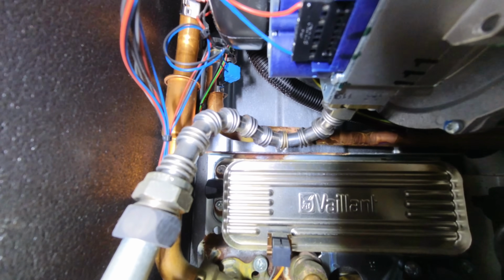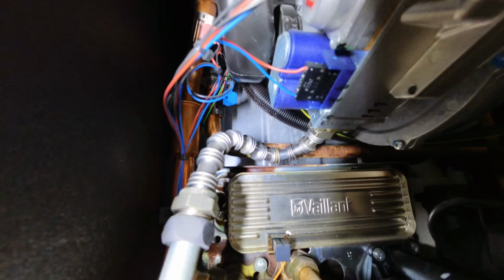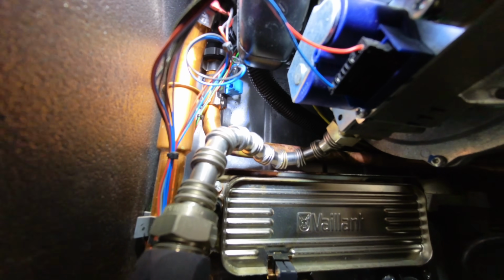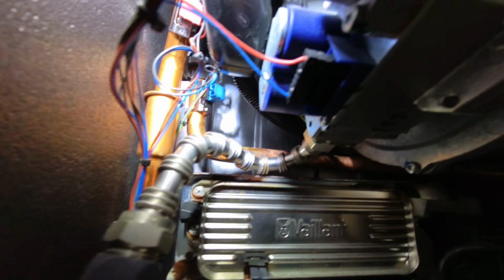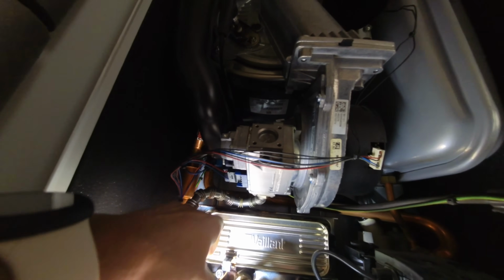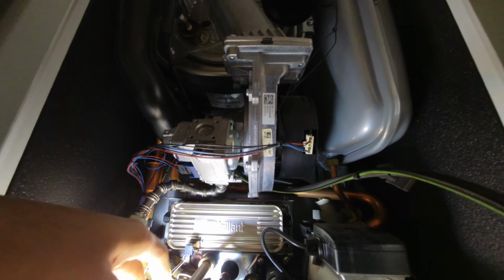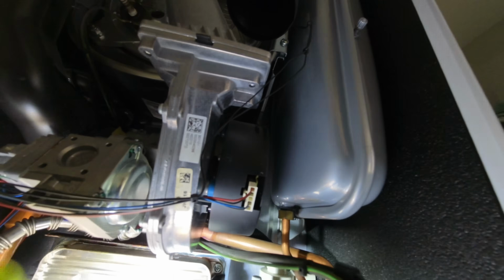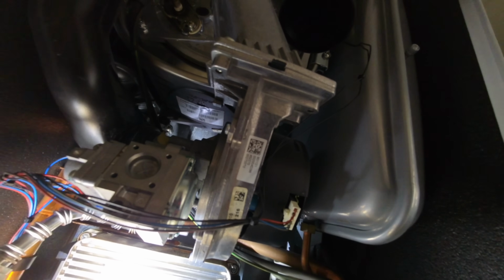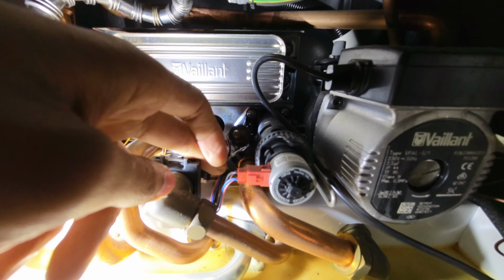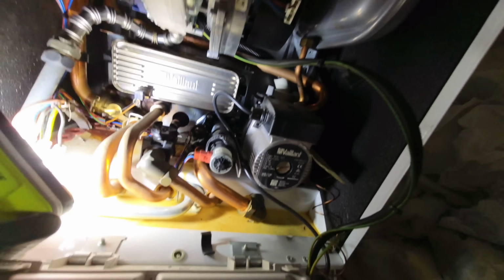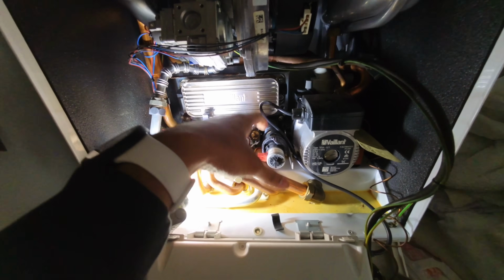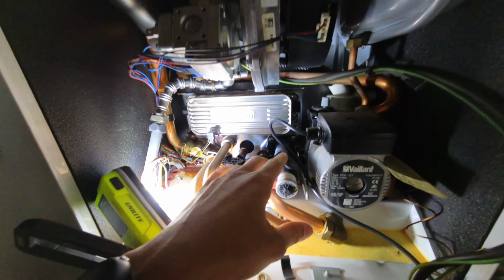As you look further up, I don't know if it shows up on the camera, but basically the condense hose has split, and that's been dripping onto the return pipe there, and off of there coming down onto the support bracket and leaking down there. And then in the Vaillant, this point here seems to be like a central point where all the water collects. So regardless of where you have leaks from, it tends to collect around that area, and that's where it tends to leak. That's where it all tends to collect, and then you think that the diverter valve is leaking, but it's not always the case.